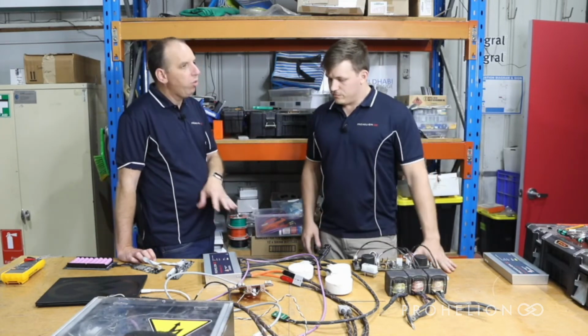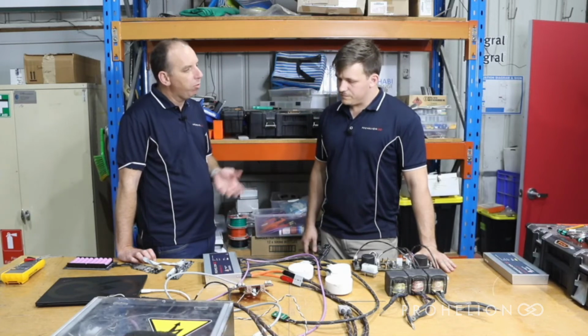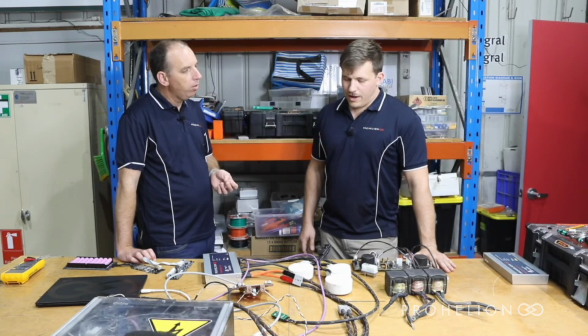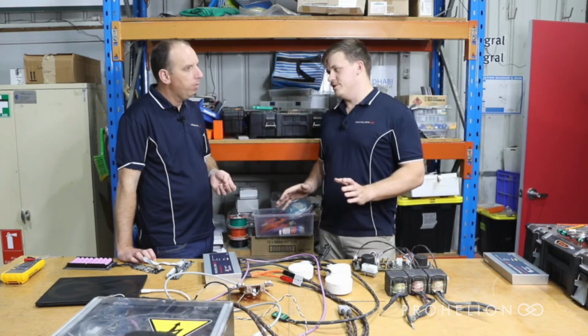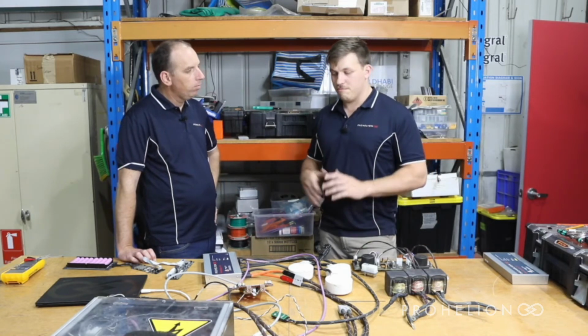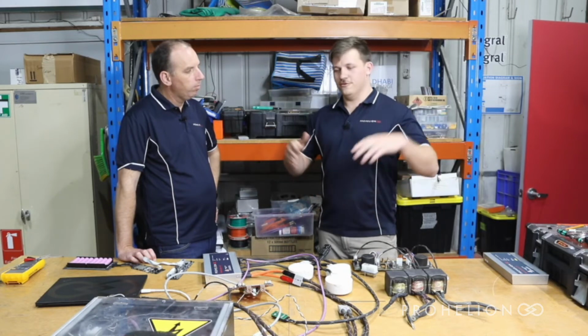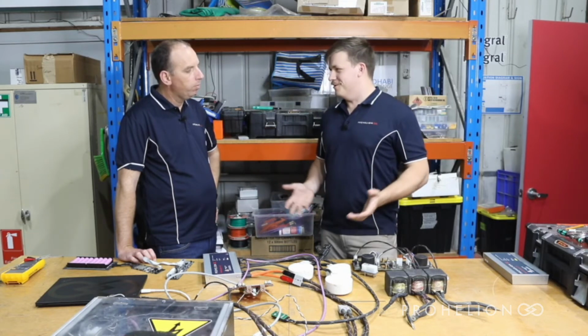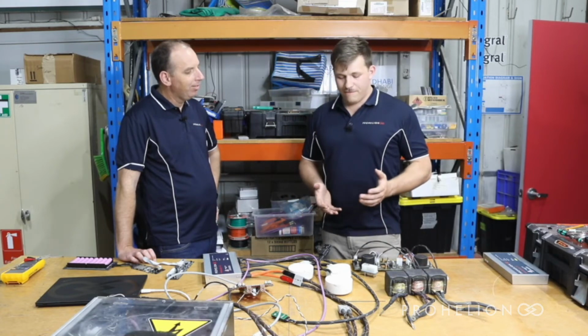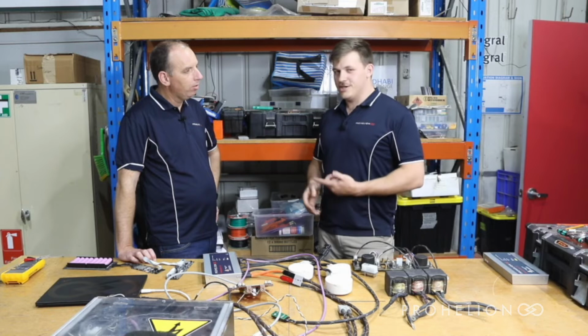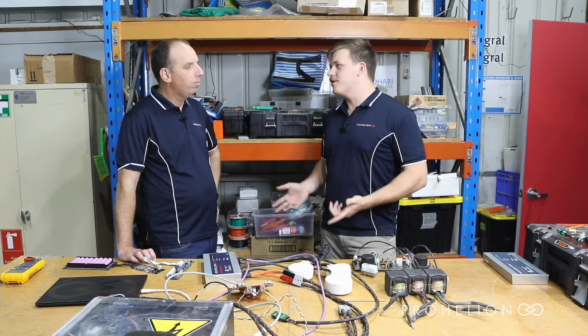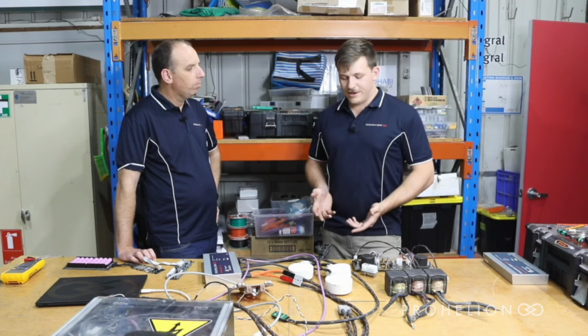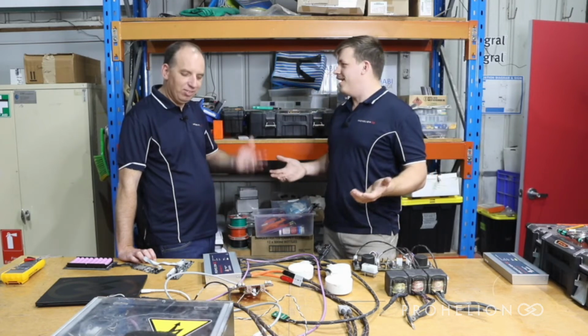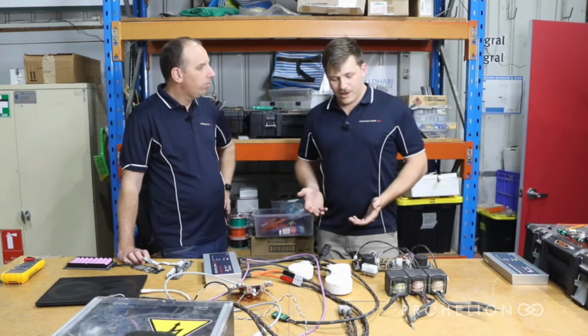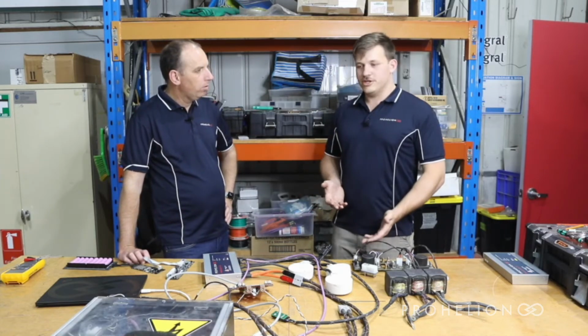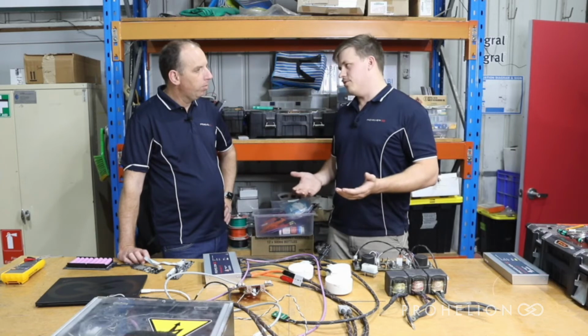What happens if you're not dealing with a motor controller on the other side of the contactors? What's the right approach then? Our recommendation is just to always have precharge, even if you're dealing with a load that's purely resistive. So if you're powering a big resistor heater or something like that, the only thing that's going to happen is precharge is going to happen instantaneously because there's no capacitor to charge, and the system's going to operate as normal. So there's really not a negative to including precharge in a high voltage battery system, which is why we always recommend that it's there.